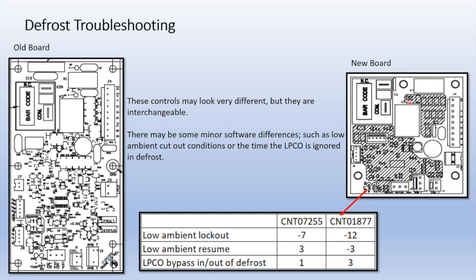A few changes. That low ambient lockout on the old board was -7. It's now -12 on the new board. Low ambient resume was +3. It's now -3. So they're running the heat pumps a little colder. The other thing is we saw some nuisance low pressure cutout trips with the older board. So it used to ignore the LPCO for 1 minute, and now it's ignoring it for 3 minutes.